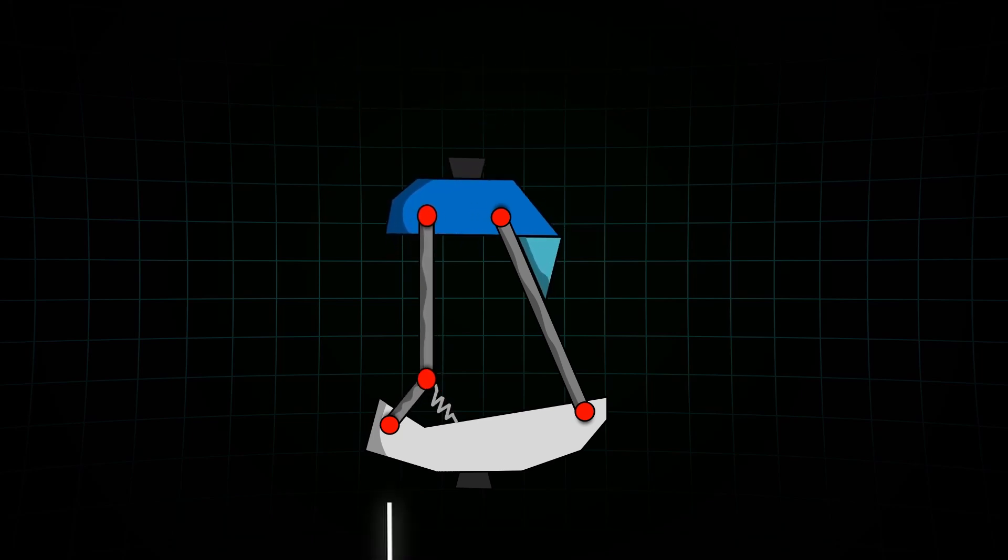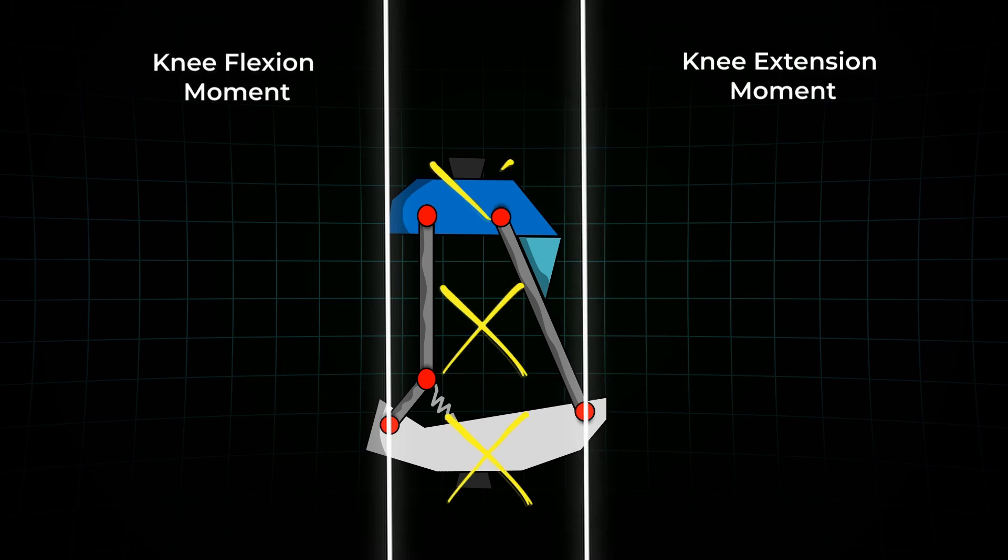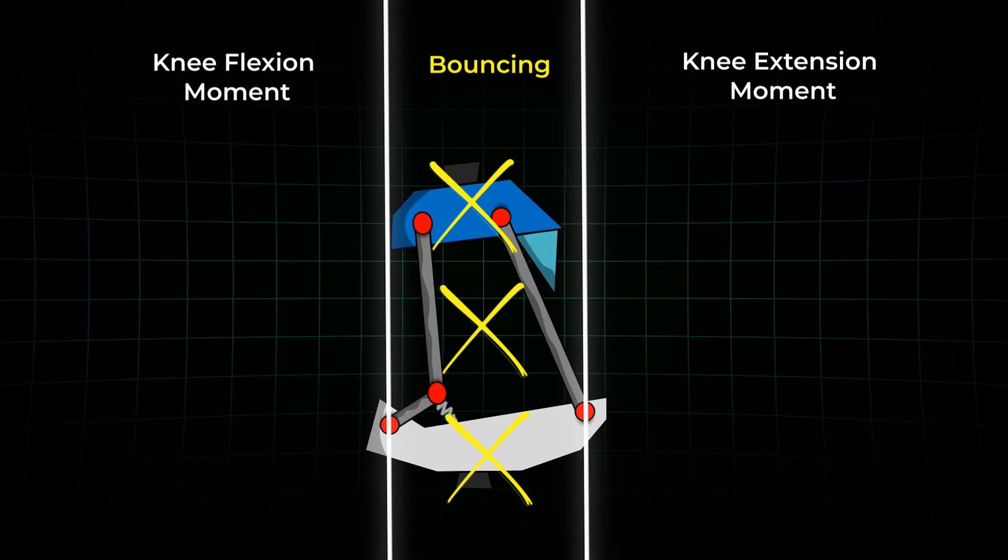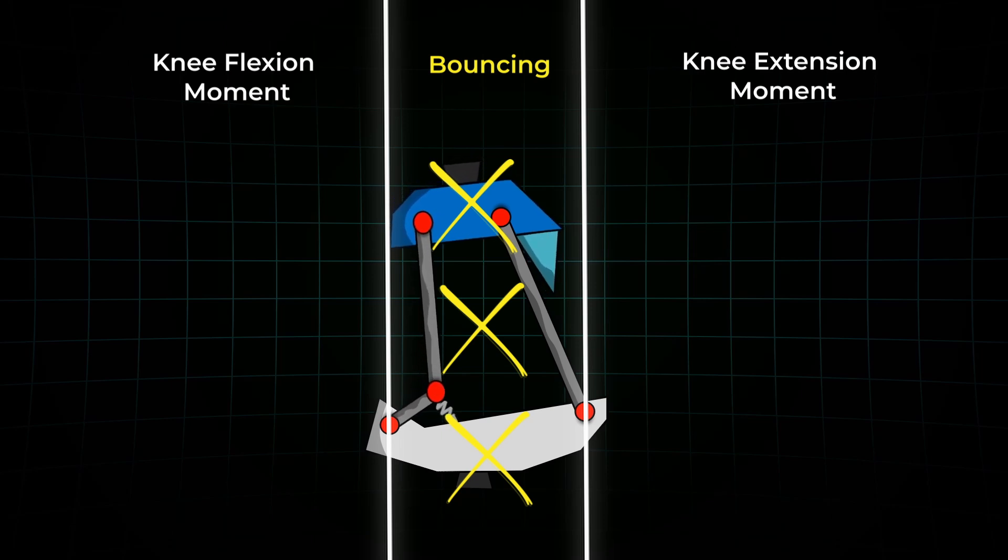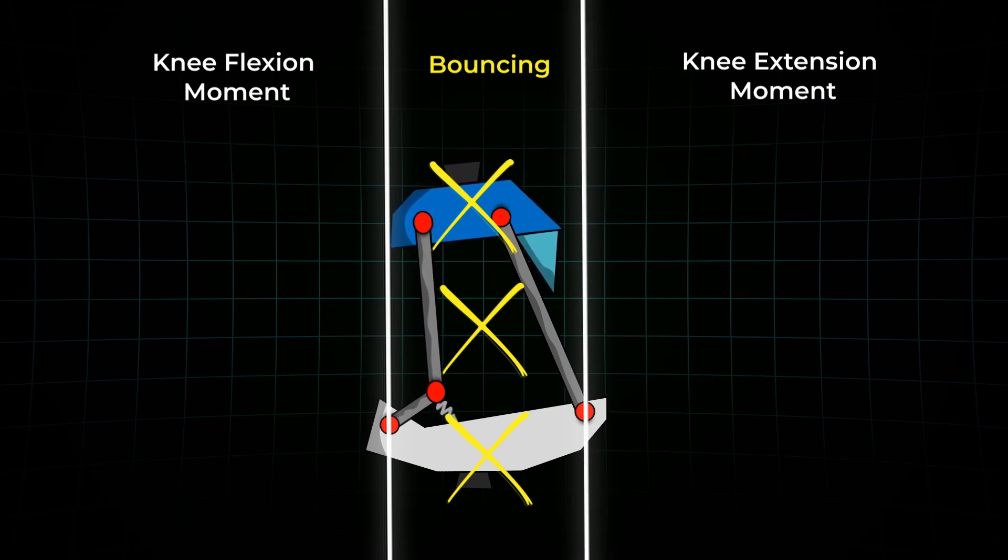It allows the knee to flex slightly under load, right at the start of the stance phase. When the ground reaction force is precisely in this area, the knee does not get flexed, but it bounces a bit in itself. This bounce effect softens impact, reduces pressure and can make the walking feel smoother, especially for users with higher activity levels.